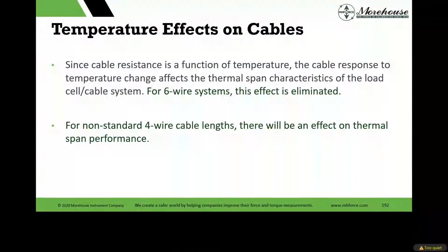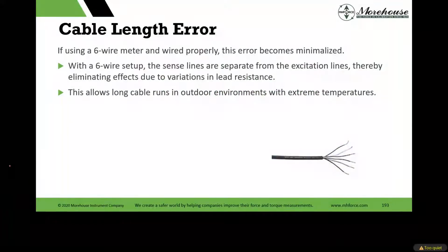But the reason is the cable response to temperature change affects the thermal span of the load cell. With 6-wire, you're running sense wires, and it eliminates it. And with 4-wire, there will be an impact. The sense lines are separate from the excitation, and basically what this does is eliminate most of the impact due to variations in lead resistance, and it allows for longer cable runs in outdoor and extreme temperatures.